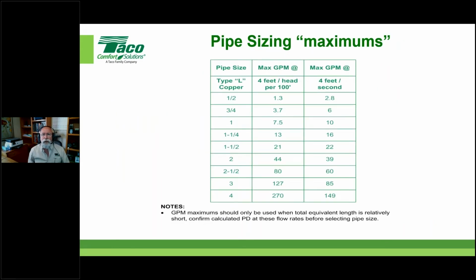So just a little review here on pipe sizing, right? We're just talking about the maximums that are out there. And again, whenever you're talking about pipe sizing, you should probably just figure out which pipe you're talking about, what type of pipe and what size is it. In this case, this little chart is just referencing type L copper, okay? But notice there's a couple different columns that say maximum. This one is 4 feet of head per 100 foot of pipe, and this is 4 feet per second. Those are 2 different ways that we look at maximums in our industry.